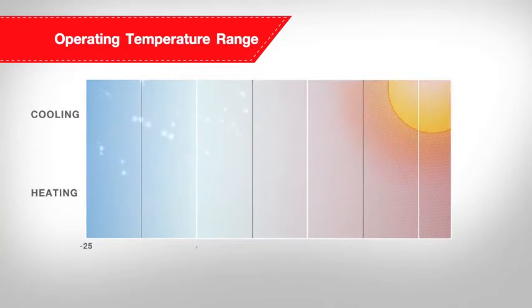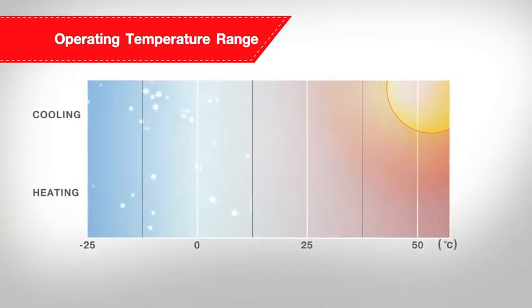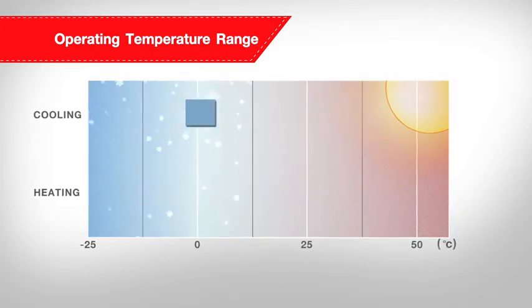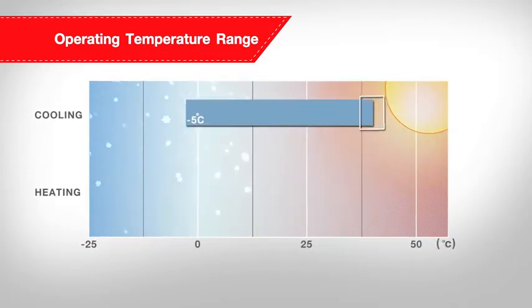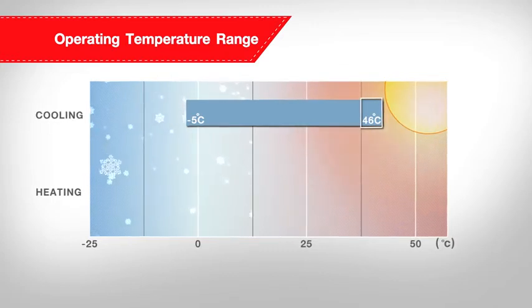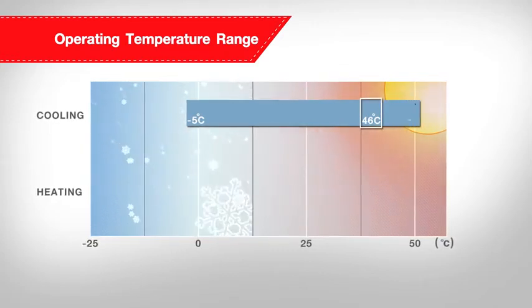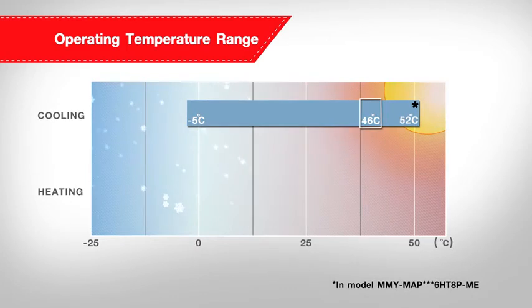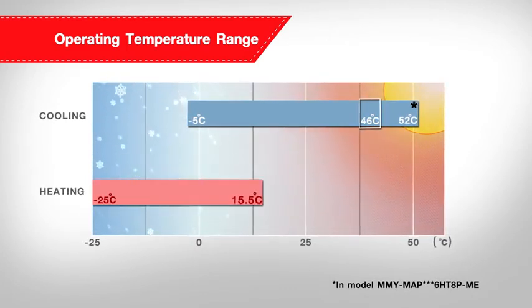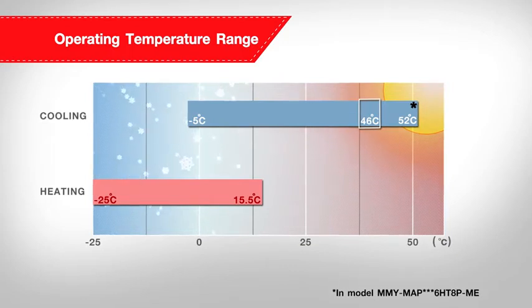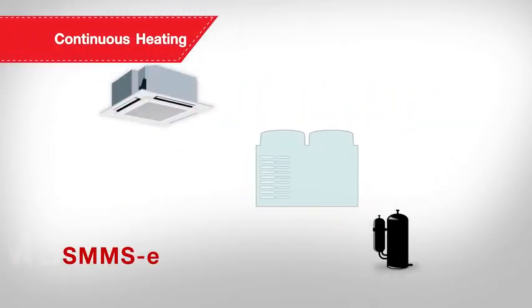With the newly designed compressor, SMMS-e can operate under a wider range of outdoor ambience, from -5 degrees Celsius to 46 degrees Celsius in cooling mode, which can reach up to 52 degrees Celsius in the Middle East model, and from -25 degrees Celsius to 15.5 degrees Celsius in heating mode.